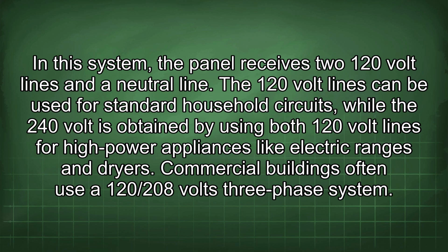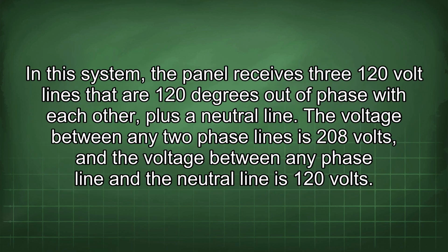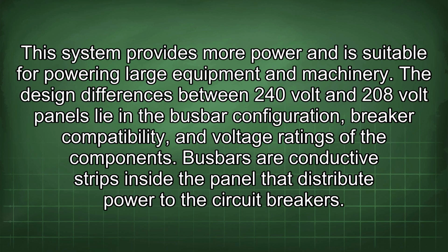Commercial buildings often use a 120/208 volts three-phase system. In this system, the panel receives three 120-volt lines that are 120 degrees out of phase with each other, plus a neutral line. The voltage between any two phase lines is 208 volts, and the voltage between any phase line and the neutral line is 120 volts. This system provides more power and is suitable for powering large equipment and machinery.